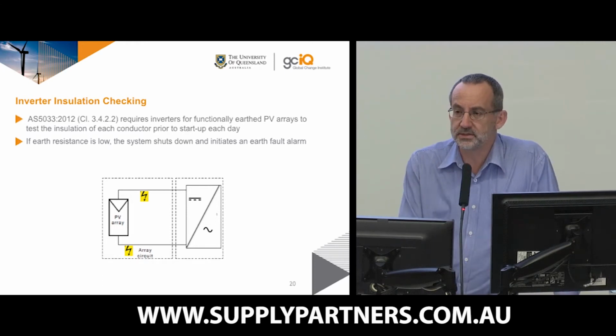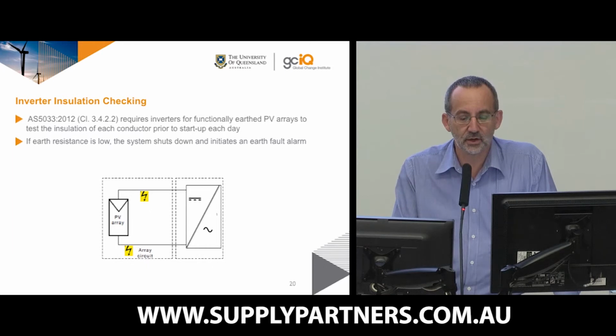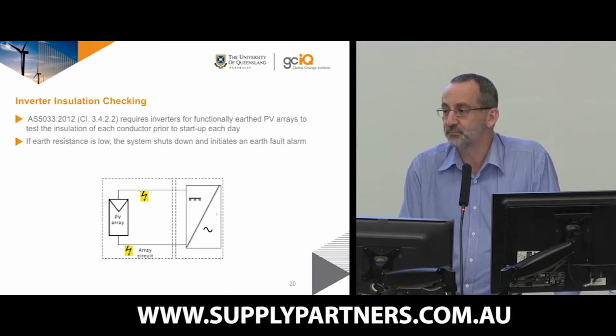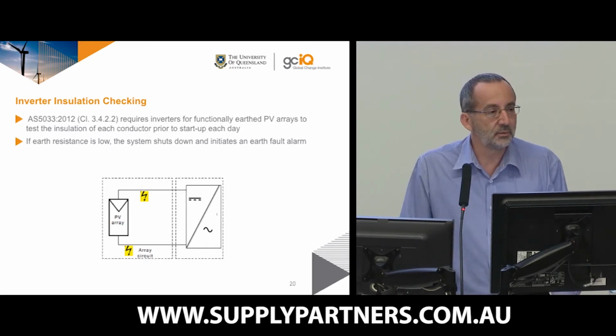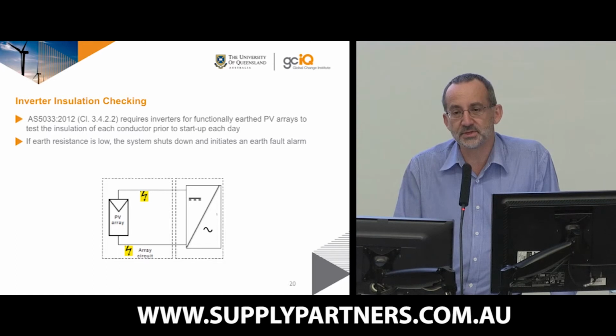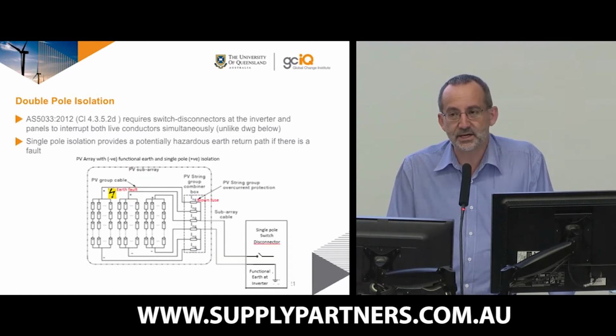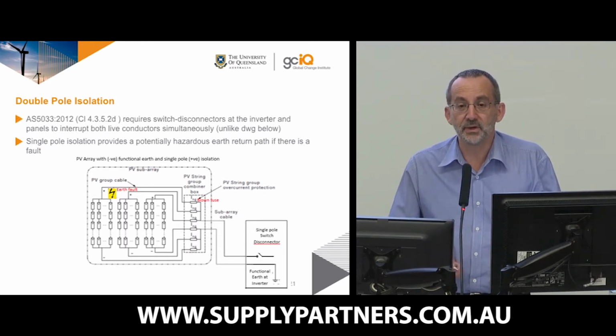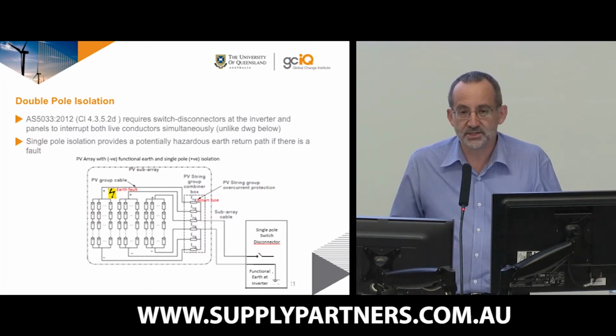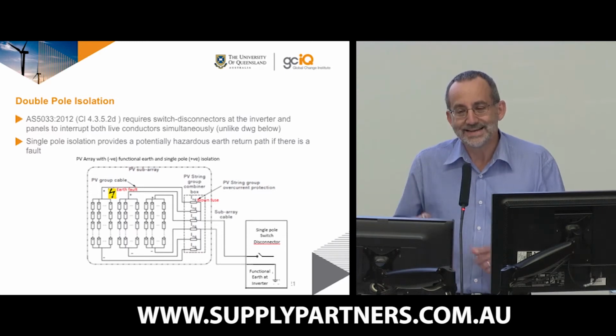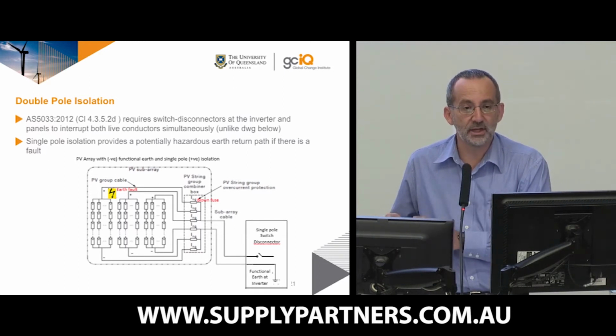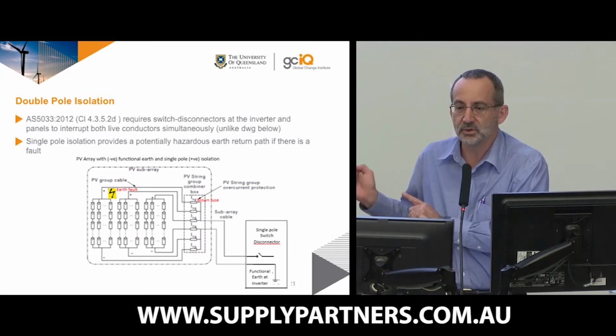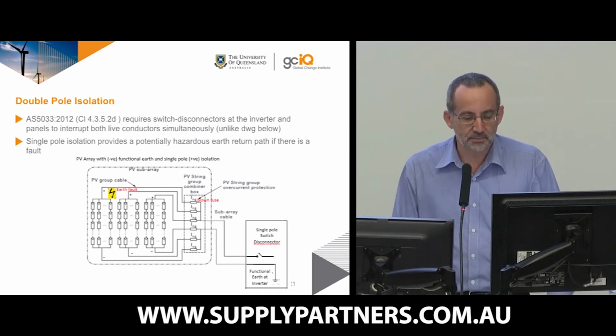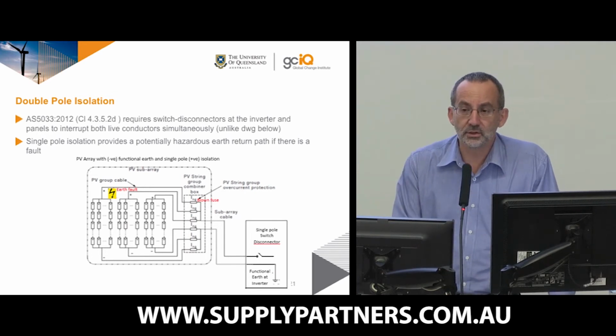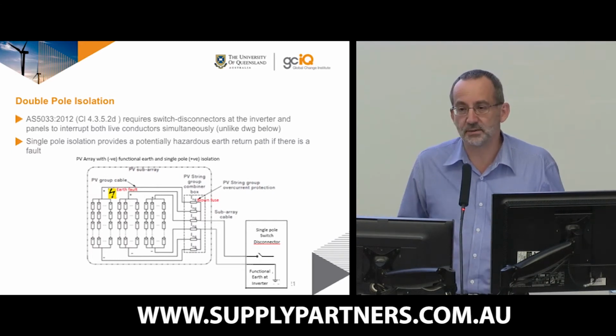Another thing that's probably worth noting is that the array out there are all negatively earthed, and unlike the unearthed systems that you're familiar with, your transformerless inverters, these larger systems have different configurations. One of the things we particularly insisted upon in our installation was that our inverter be provided with the capability to check the insulation each morning. That's an AS5033 requirement, which, particularly now that the new 5033 only applies up to 240 kilowatts, larger arrays will not have to have, but we insisted upon it. So each morning the inverter looks at the positive and the negative. If there's any leakage to ground, it says, I'm not going to start off today.